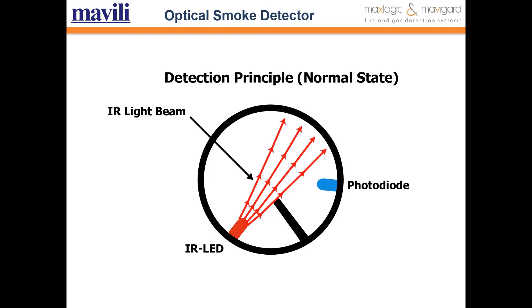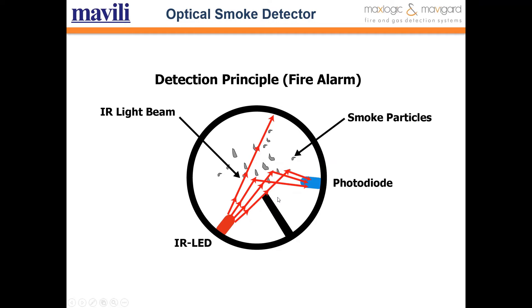Regarding the optical smoke detector detection principle: there is an IR LED transmitter. In normal conditions, the light does not reach the photodiode receiver. But in the case of fire, the inside of the smoke detector fills with smoke particles. The IR LED beam strikes the smoke particles, changes direction, and reaches the receiver. The detector then triggers the fire alarm signal.